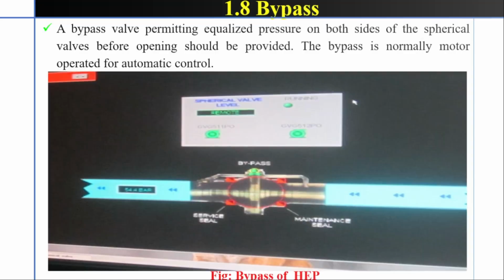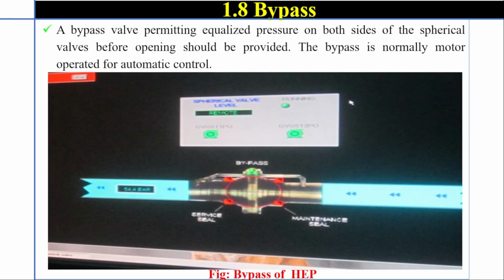This figure indicates the inlet valve of a hydroelectric power plant. A bypass valve permitting equalized pressure on both sides of the spherical valve before opening should be provided. The bypass is normally motor operated for automatic control. As you can see, this is the bypass of a hydroelectric power plant.